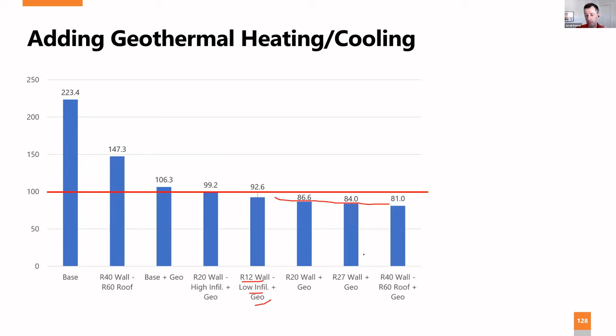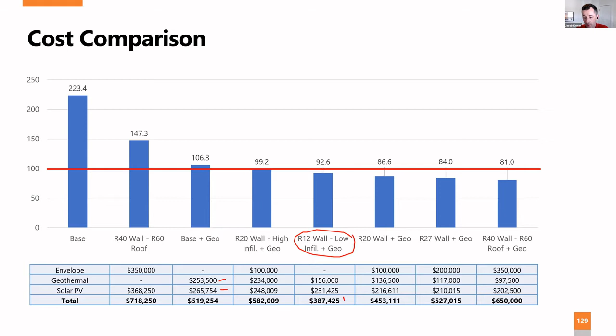And so when we compare the cost of the envelope, call it 350, and the solar PV we would need, which in this case would still not get you net zero because it's natural gas. But adding geo for 253,000 reduces the amount of solar. And so when we go through all of these scenarios, we found that the cheapest is to leave the walls as is. It makes the geo system bigger than if the envelope was better, but the optimal is much better if we simply use the efficiency of the geo system. So again, the takeaway is that geo is the easiest way to net zero. The envelope improvements probably won't make financial sense.